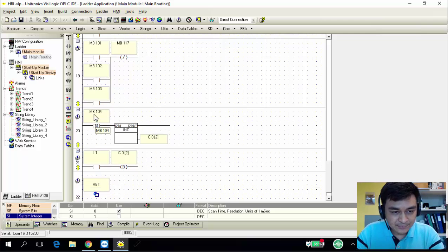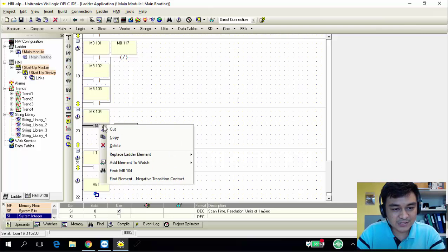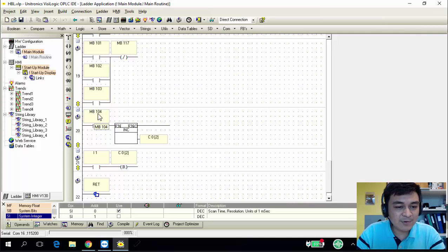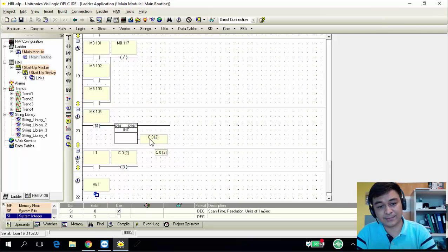I'm using MB104 as a counter trigger using negative edge. First get it from the positive P contact, then right-click and change it to negative pulse. Every time my counter reaches the last number, I increase the counter by one using an increment counter. Get the increment counter from the math functions. Create counter C0 with a value of 2.